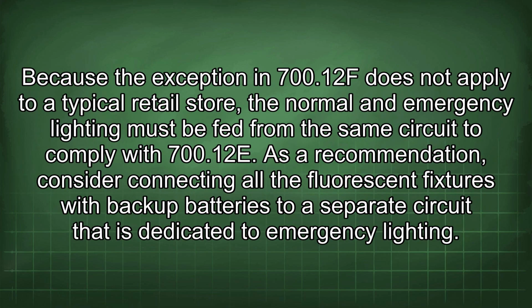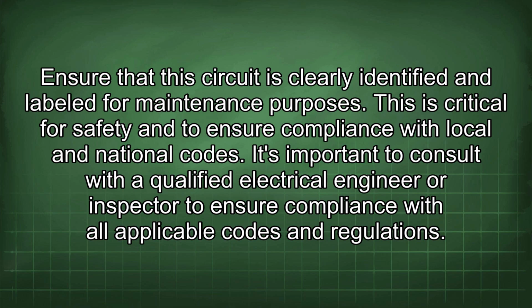Because the exception in 700.12(f) does not apply to a typical retail store, the normal and emergency lighting must be fed from the same circuit to comply with 700.12(e). As a recommendation, consider connecting all the fluorescent fixtures with backup batteries to a separate circuit that is dedicated to emergency lighting. Ensure that the circuit is clearly identified and labeled for maintenance purposes. This is critical for safety and to ensure compliance with local and national codes.